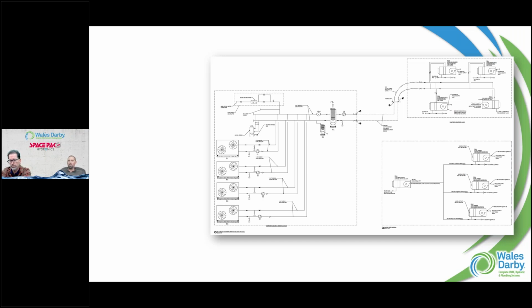With an air to water heat pump standalone doing primary heating, you're checking heat exchangers, putting the system on, making sure everything operates, making sure the insulation on the pipe is still there if it's a chilled water application. Then the most important one is water quality, right? If we're putting glycol into that system, we want to monitor the level as well as the pH of the system—it's not going to last forever, it can break down, and if you have materials like you were just saying, it can really make a mess. So that's really your maintenance: water quality, making sure your heat exchangers are clear and the system's operating properly. That's really it, not much to it.